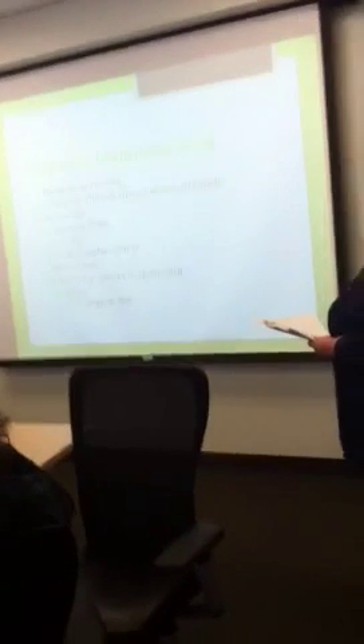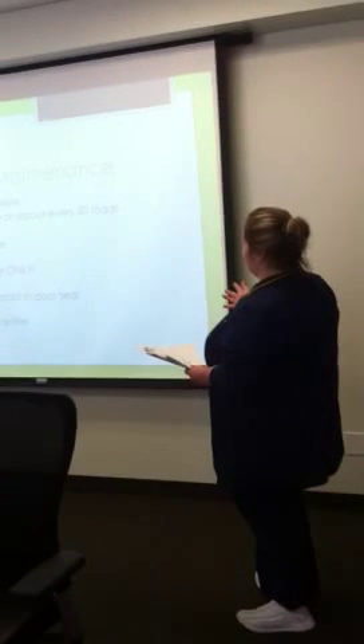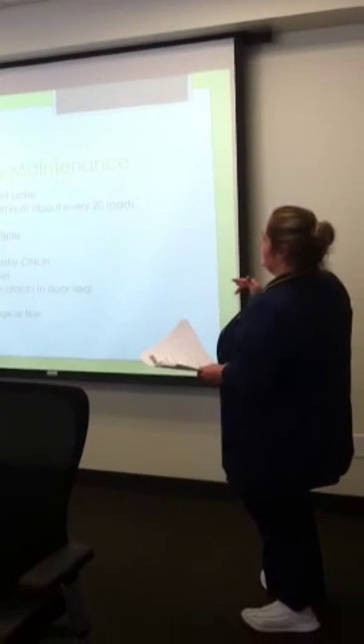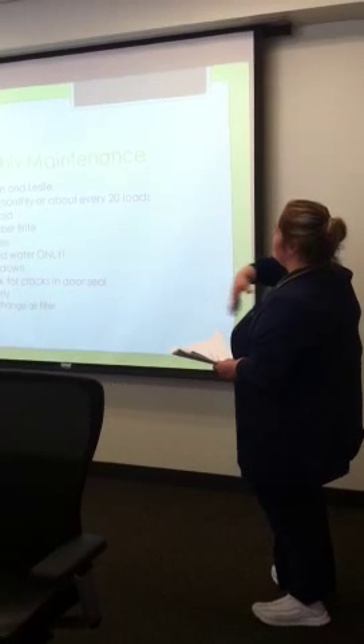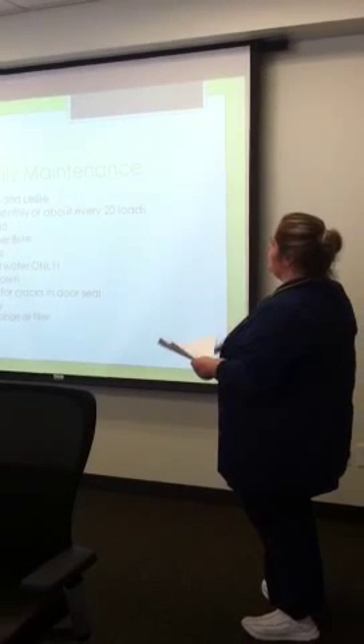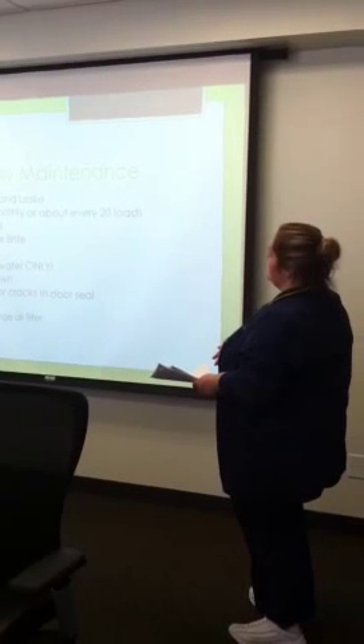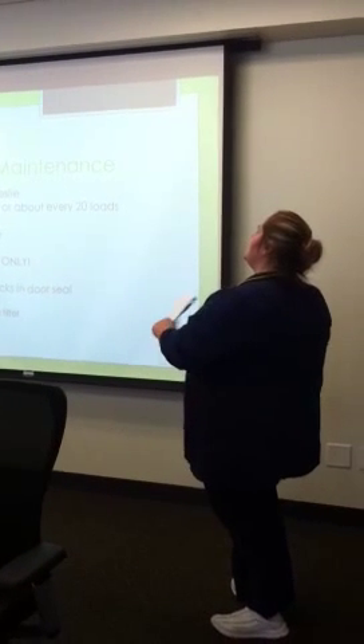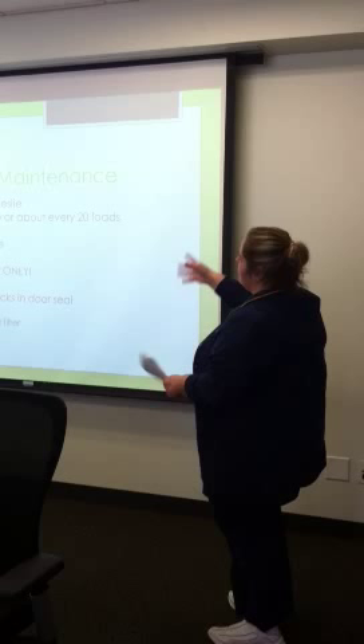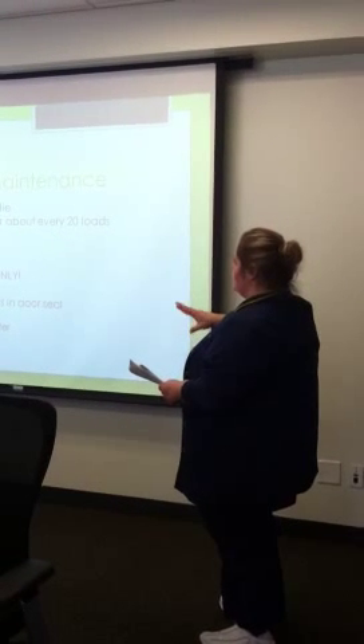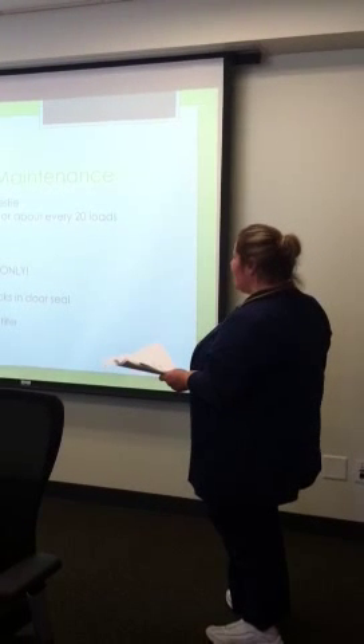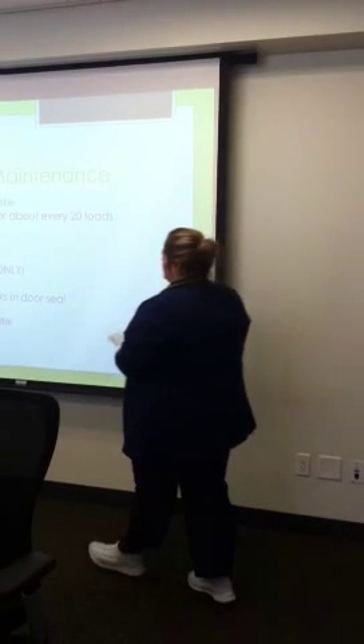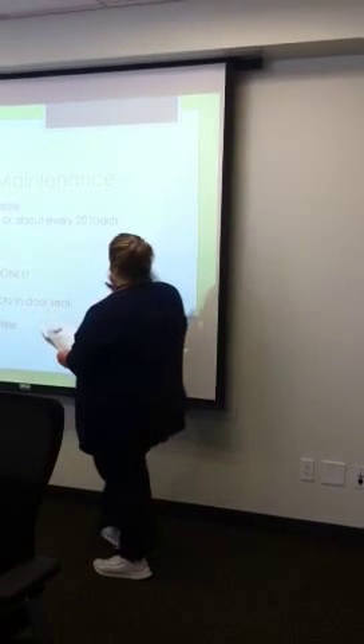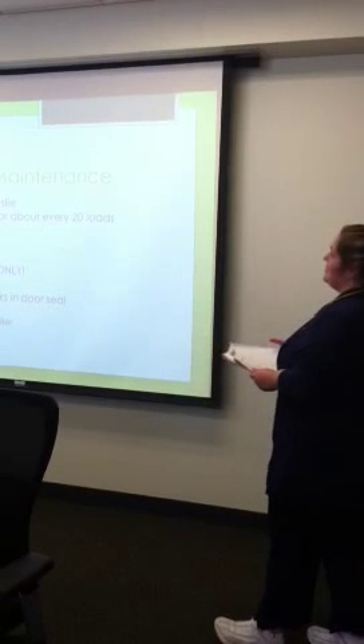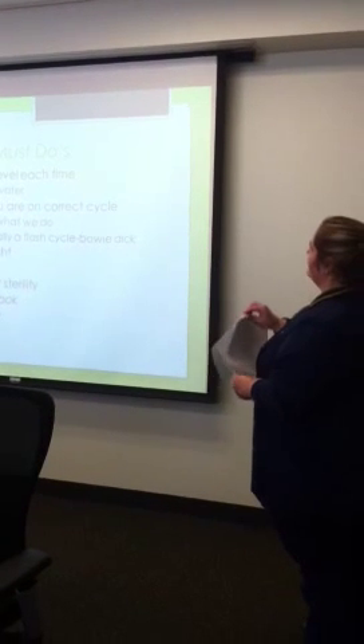All right, so the monthly maintenance, again, is done by Leslie and myself. It's done once a month or approximately every 20 loads. It has to be done when the machine is cold. We put a cleanser in the bottom of the machine. We run a cycle through. We empty out that water. We refill it with clean water. We run the cycle through again. We empty out that distilled water only. We fill it back up again, wipe it down, check the seals. And that's what we run monthly. And then once a year, we change the air filter, which I just did in September. So these are things that you guys don't need to worry about, but just know that they are being done.